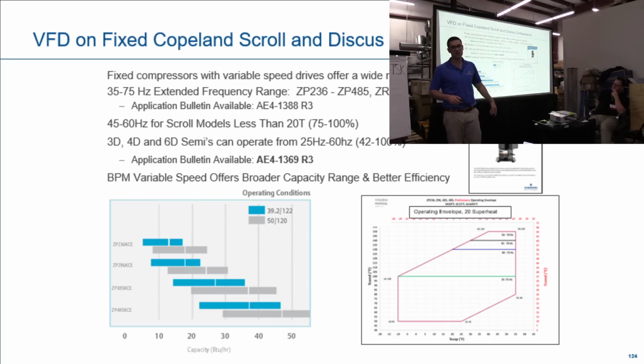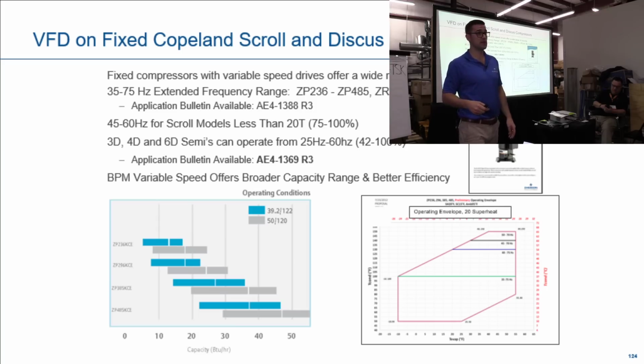So what's going on right now is we have a lot of people ripping out Copeland compressors and putting a drive compressor on racks. Well, why rip out the compressor when you can take a variable speed drive and just put it on there right now? Pretty important stuff.